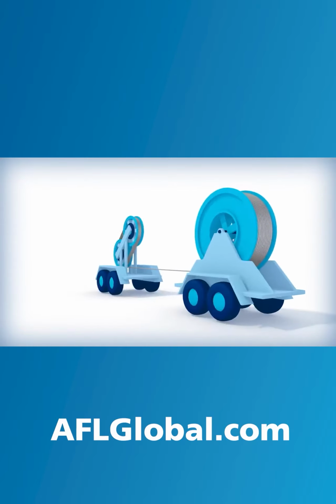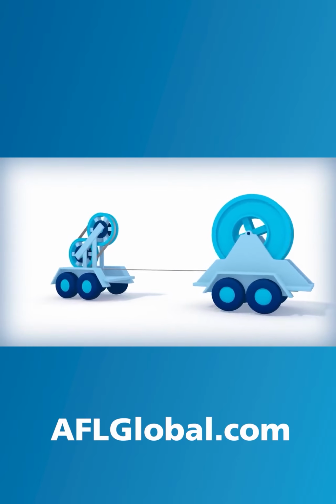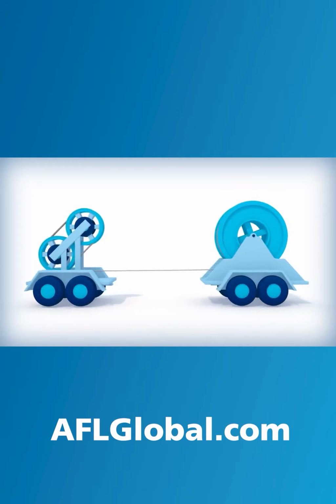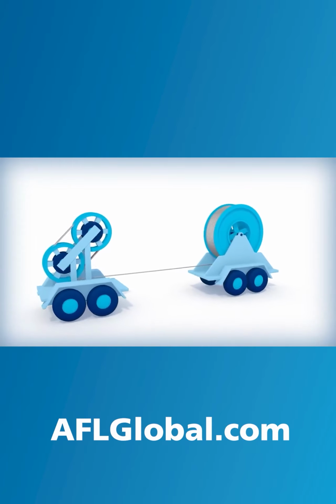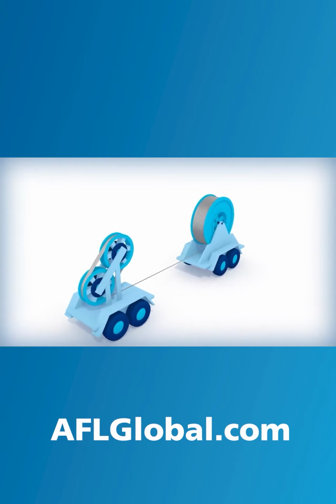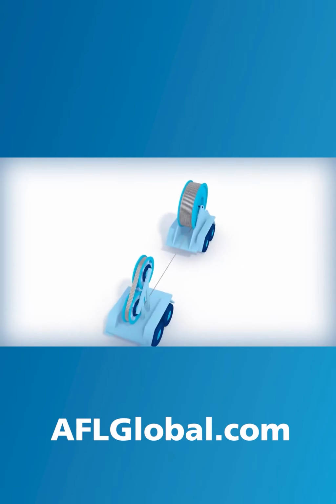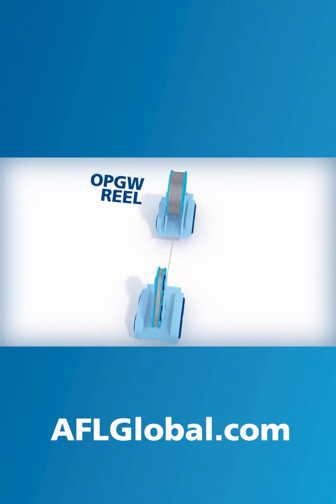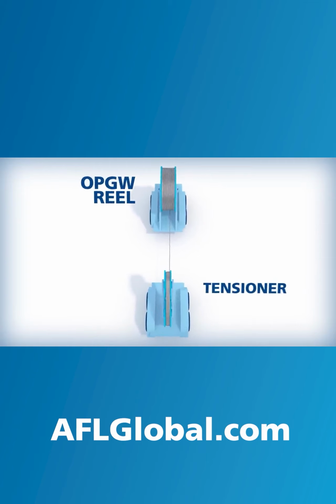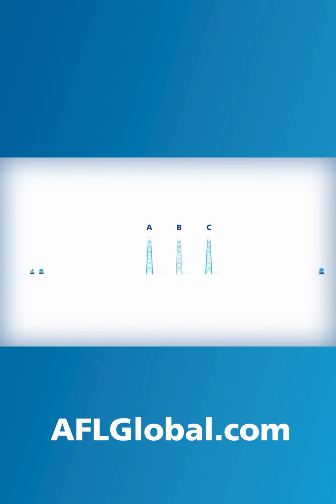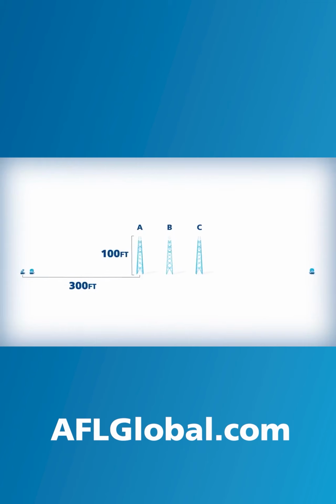Because the OPGW reel is not designed to withstand the braking forces that arise during stringing, AFL recommends using a multiple groove bullwheel tensioner. The OPGW reel should be placed directly in line with the tensioner, and the OPGW should be reeved through the bullwheel properly. The tensioner should be located at a 3:1 ratio to the stringing block on the first structure and also be in line with the first two structures.